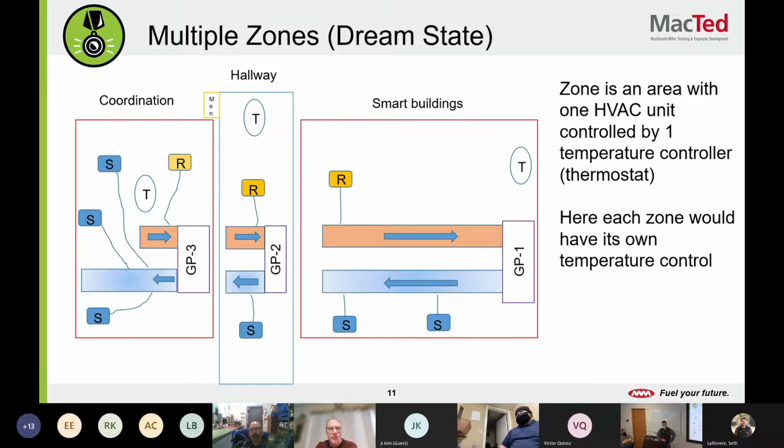Any other options than that without just adding new equipment? Suppose you can look at airflow balancing. Sometimes the rooms have changed their use. When these rooms were installed, each of these registers, when he talks about the CFM, cubic feet per minute of air, each one was designed to output a certain amount that keeps this room to the design conditions. Well, if we just subdivide the room and start changing the use case, maybe that changed, but they never went back and rebalanced the air to redistribute the amount of heating and cooling. So there's a lot you can do to make the best with what you got, up to a point.